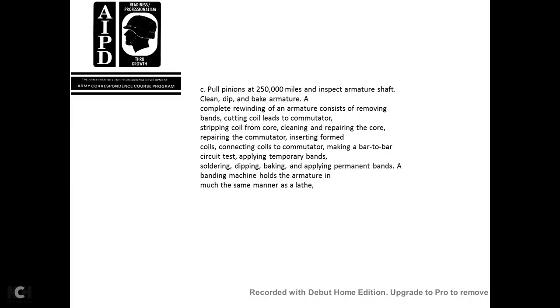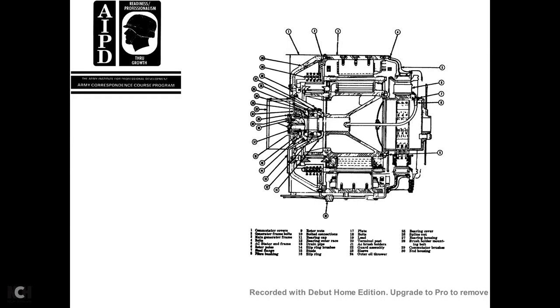Complete rewinding of the armature consists of removing the bands, cutting coil leads and commutator, stripping the coils off the core, cleaning and repairing the core, repairing the commutator, inserting formed coils, connecting the coils with the commutator, making the bar-to-bar circuits, testing, applying the temporary band, soldering, dipping, and baking, and applying the permanent bands with a banding machine, held in much the same manner as in a lathe.